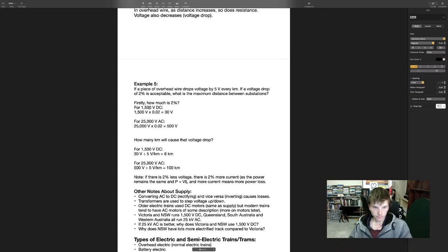So for 1500 volts DC, we just go 1500 times 0.02, that's 2%, equals 30 volts. Cool. So this tells me that we can drop the voltage by 30 volts before, on a 1500 volt system, before we need a substation, if this 2% number is to be the most acceptable figure.